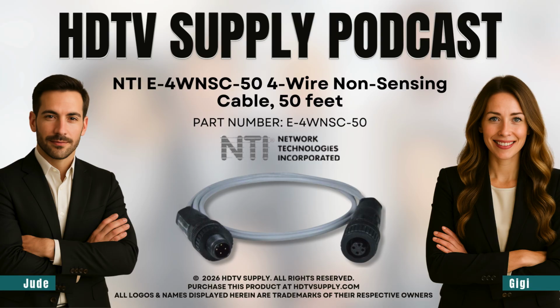Exactly. And then you have the connectors. These are M12 4-pin connectors. I did notice those. They look way more industrial than my laptop charger. They're heavy duty. Think about a USB plug. You bump it, it just falls out. In an industrial setting with vibrations and people working, you can't have cables slipping out. M12 connectors physically screw in and lock. They are built to survive in pretty harsh environments. And speaking of that, the spec sheet says it operates from 14 up to 140 degrees Fahrenheit. Which covers everything from a freezing cold server aisle to, say, a sweltering boiler room. It's built to be resilient.